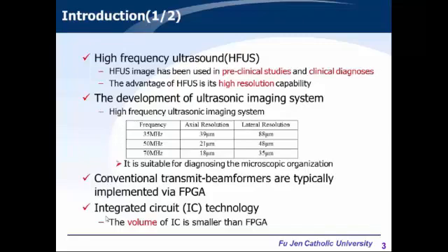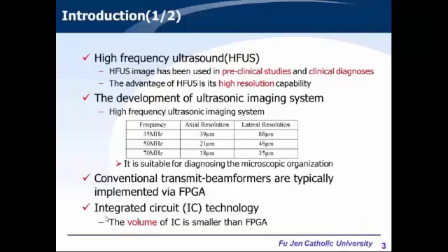High-frequency ultrasound has been widely used in preclinical studies and clinical diagnosis because it can provide superior resolution. As the frequency increases to 70 MHz, the axial and lateral resolution will achieve 18 and 35 micrometers. Therefore, it is suitable for diagnosing microscopic structures like eyes and skin. In general, transmitted beamforming is typically implemented by FPGA, but we prefer IC technology because the IC die size is smaller than FPGA, and there are other reasons we will discuss later.